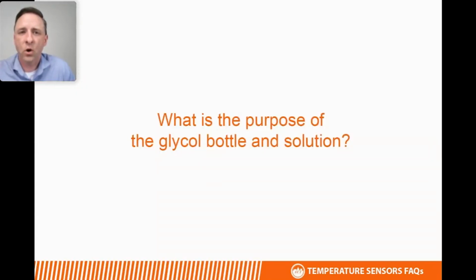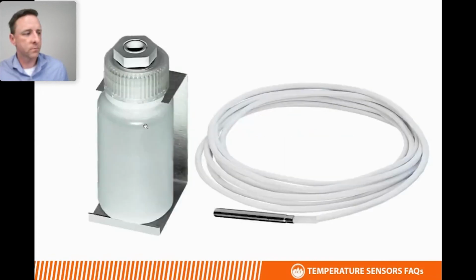For low temp freezer glycol bottle sensors, the common question is what's the purpose of that glycol bottle and that glycol solution? And the purpose is to act as a thermal buffer, which in essence slows the response time of the sensor. And so the idea is if you've got a large cooler freezer, you don't want to open that door and have the sensor hit with a rush of room temperature air. Could send the system into alarm. And so the sensor is installed into a glycol bottle, which then acts as a buffer, slows the response time, and allows the system to trend the longer term fluctuations in temperature. It avoids unnecessary cycling of the cooler, the heat or the cooling system, for when it would get a shock of that room temperature air.